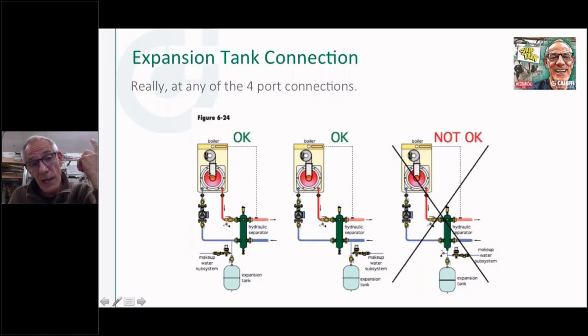Here's the problem with these high pressure drop boilers. If you pump into the boiler, the delta P that this circulator can develop when it's spinning shows up as a positive pressure in here. So what happens on a lot of these little tight heat exchanger type of boilers, they have pressure switches on them. And if you don't maintain the pressure, usually about 8 PSI, I think is what those pressure switches are, if you don't have enough pressure going into that, you're going to lock out on that. And you know what? I'm going to show you that next week. You got to come back next week.